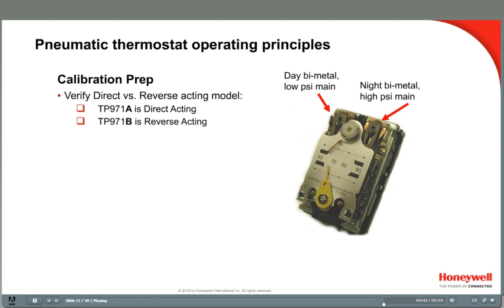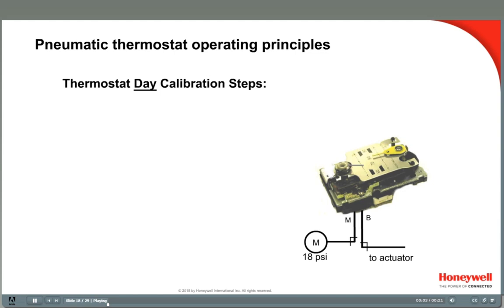In the following calibration examples, I will use a direct acting thermostat. Be sure to follow manufacturer instructions for the type of thermostat you are working on. Here are the steps to calibrate a 2 temperature thermostat. Step 1 you have already done — verify the main air supply at the thermostat. To calibrate the day set point, make sure you are applying the day pressure, 18 psi in this example.